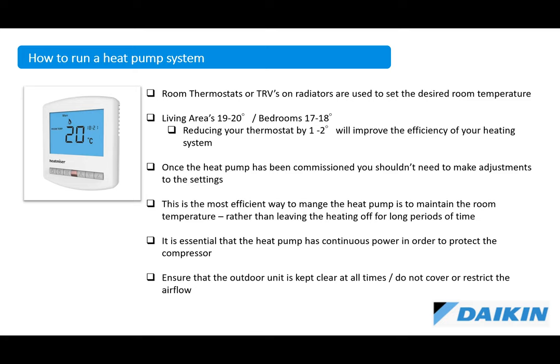So today it's cold outside. It's going to be putting a higher flow temperature into your heating system than it was last week when it was, say, 16 degrees outside. So it gives that fluctuation, and it means that the heat pump is always matching the flow temperature in the building to what the actual outdoor temperature is. So you've got a really nice synergy going on there.